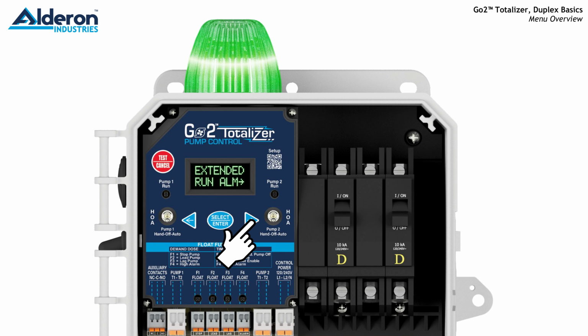Under Extended Run Alarm parameter, you can program an alarm to be activated if the pump has been running past the programmed time. For example, if your standard pump run time is around 2 minutes, you can enter a time of 4 minutes to activate the alarm if the pump is running 4 minutes or greater. This could be because of a float failure or problems with the pump discharge that could be plugged or have a broken pipe.